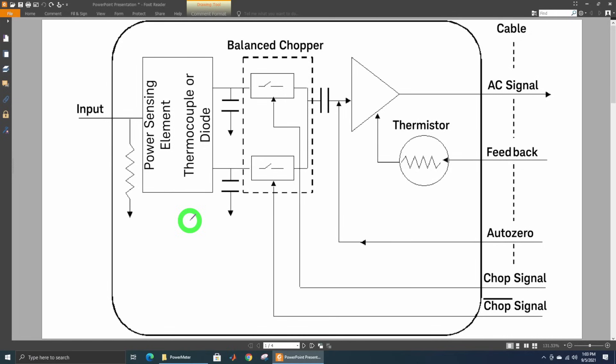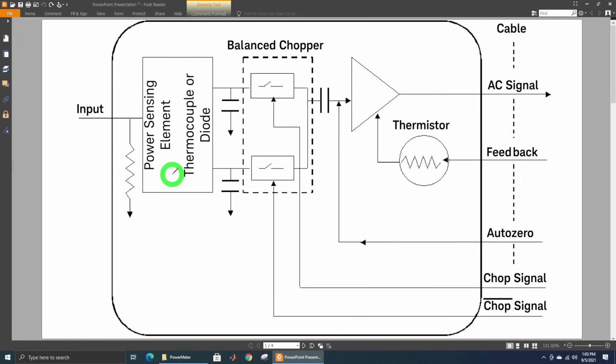The easiest way to make a power sensor would be to dissipate the incoming RF energy into a resistor, converting that RF energy into heat. Then you can measure the change in temperature with reference to some other component that's not receiving RF power. From that, knowing the environment and thermal resistance, you can find out the RF power. But if the power is very small, the change in temperature would be very small also, so measuring very low power signals in the minus 70 or 80 dBm is going to be very difficult using a thermal method.